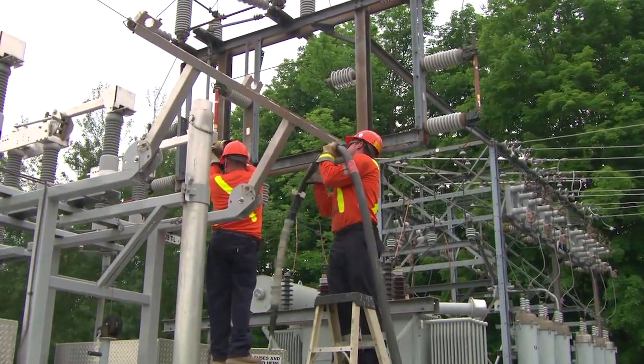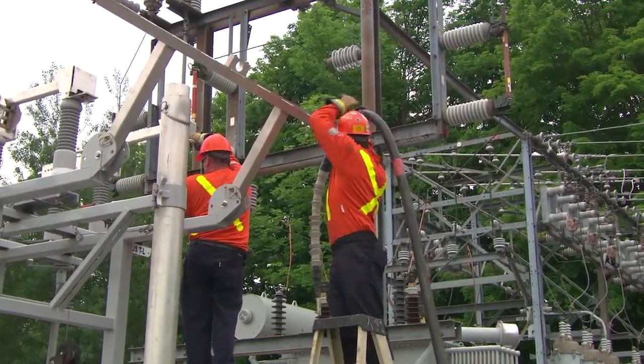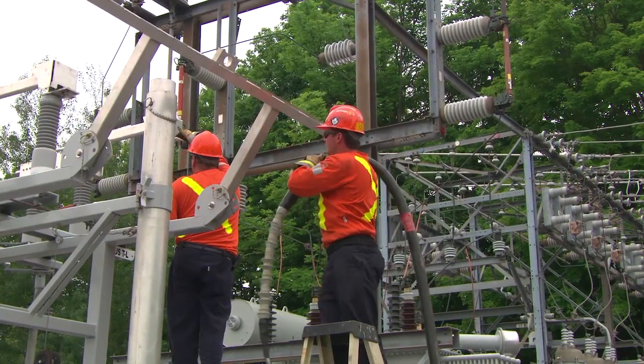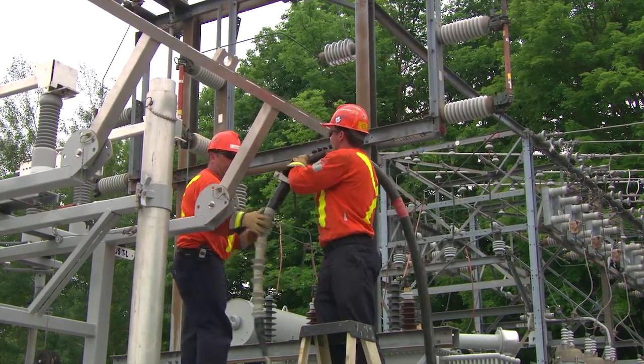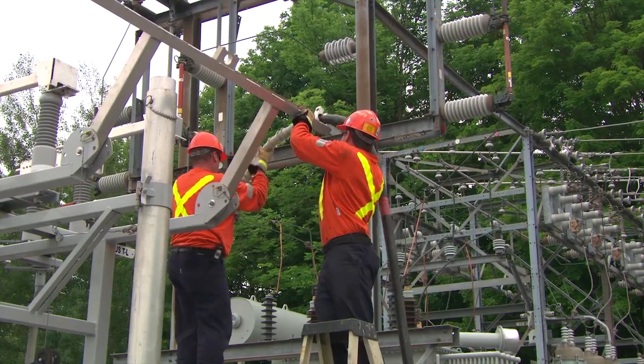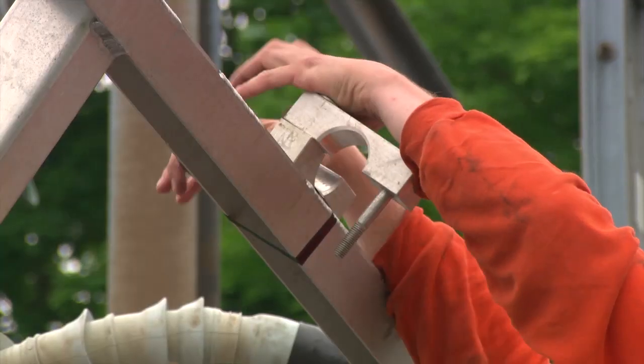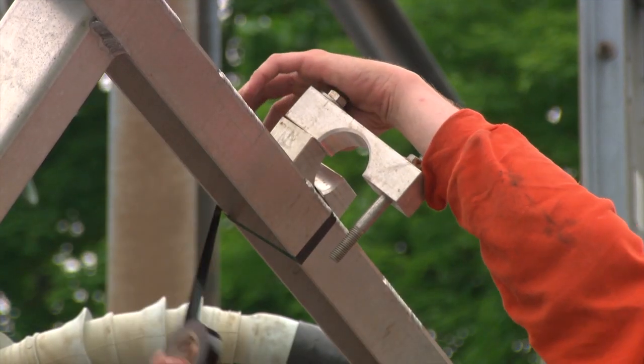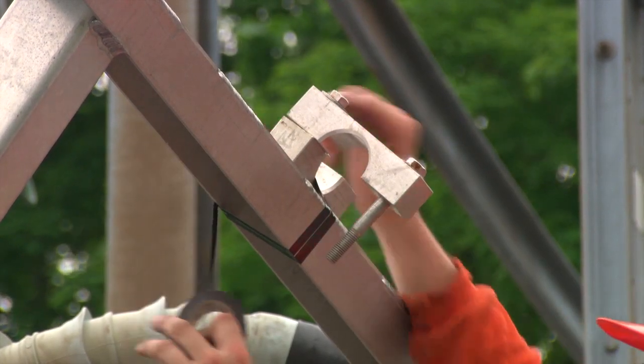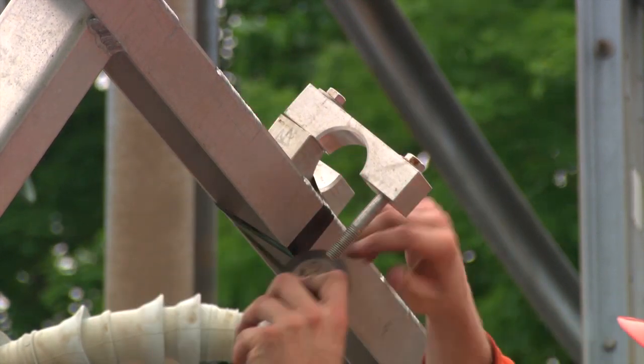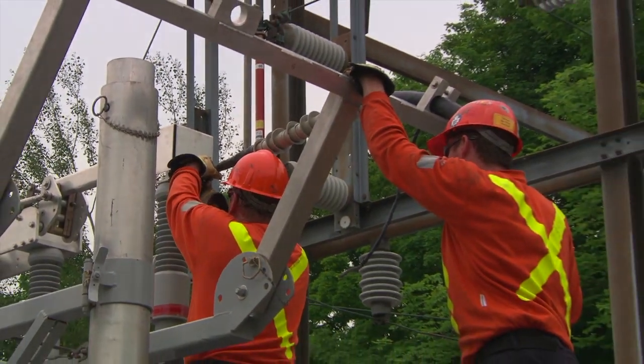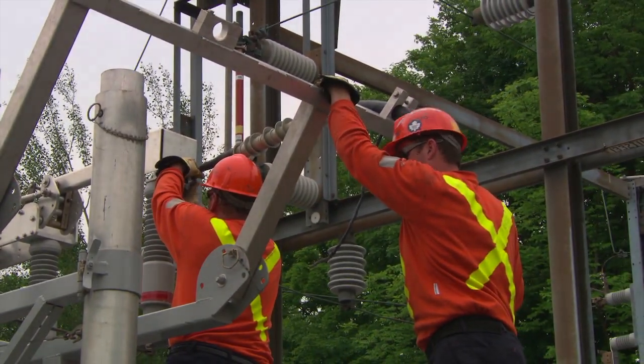Using the 2-piece cable blocks, secure each phase over the top of the bracket. Lining up cables, cable blocks, bolts, and bracket will require some finessing. In this case, electrical tape was used to hold half of the cable block in position. The final secured position of the cable should allow for some movement due to thermal expansion.